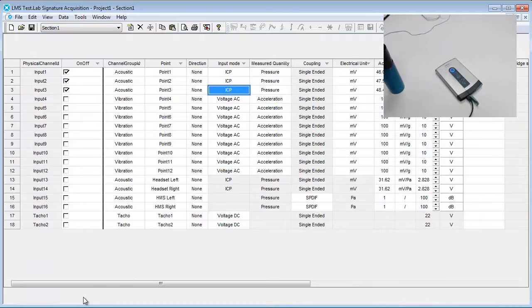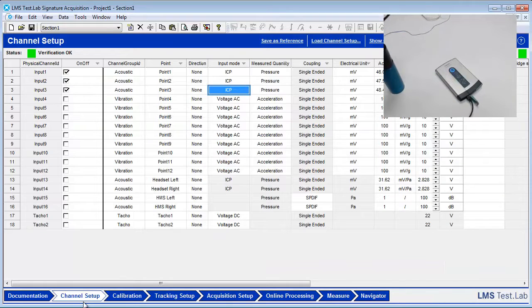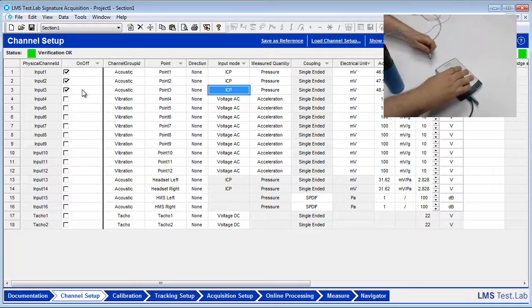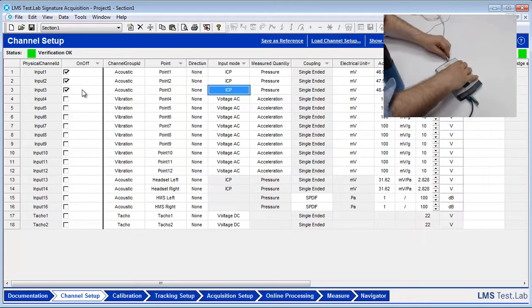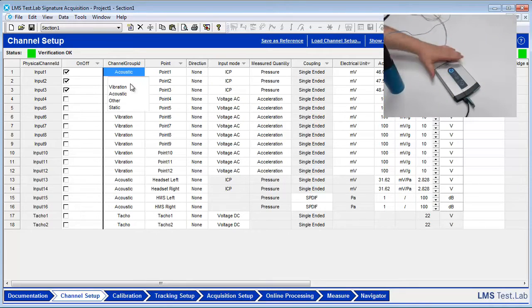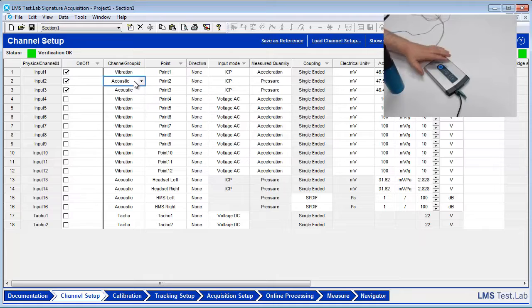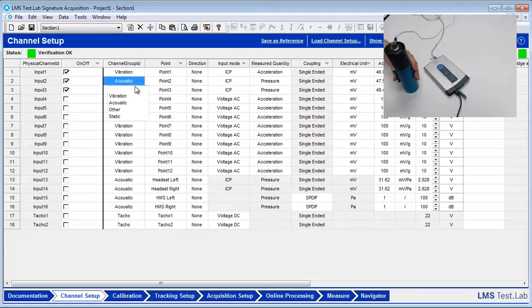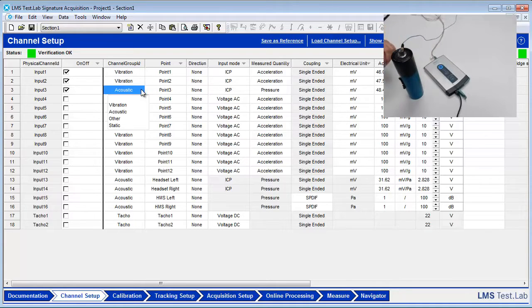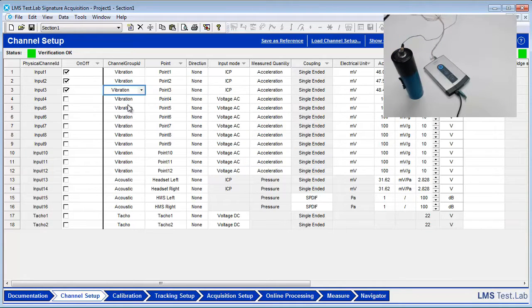Go back to the channel setup worksheet. Ensure that the first three inputs are checked on. Set the channel group ID to vibration. Set the directions appropriately.